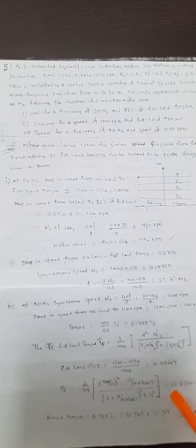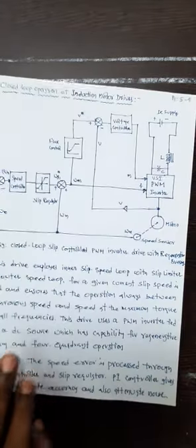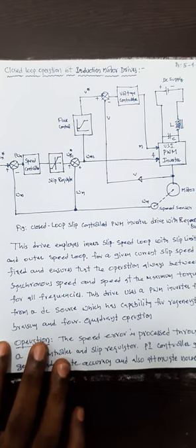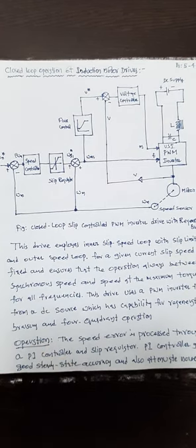and it should be 25.37 Newton meter. So therefore, substituting in this formula, torque is equal to 0.769 into 25.37, which gives 19.51 Newton meter. So these are the problems. These are some of the familiar problems belonging to the stator voltage control method as well as the frequency control method. So let us start the next topic, which is the closed loop control of induction motor drives.